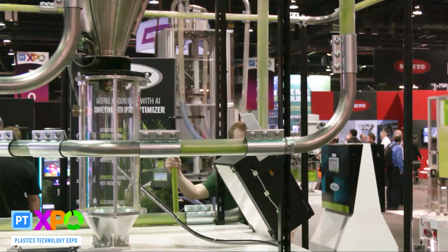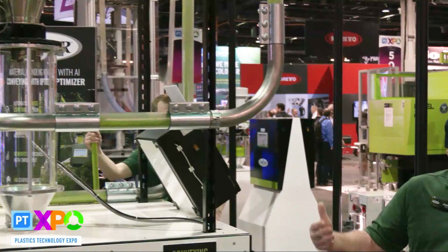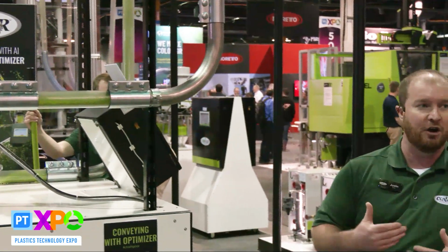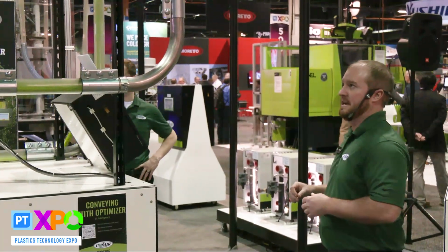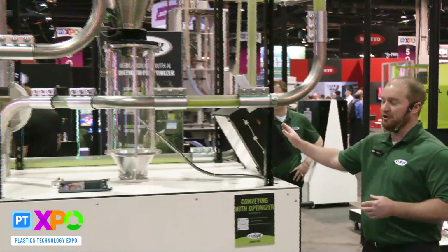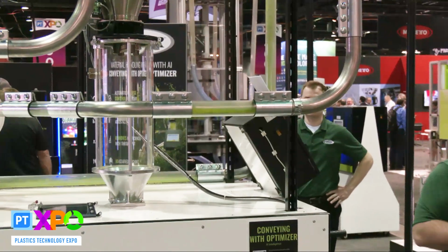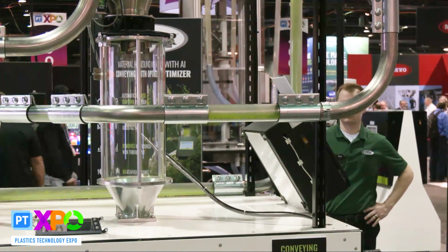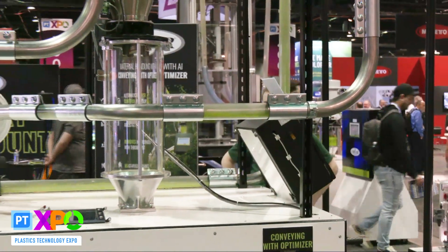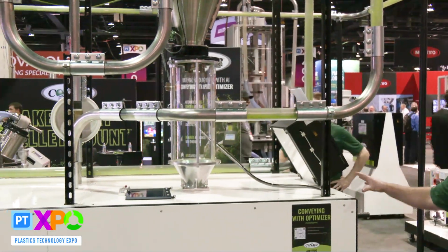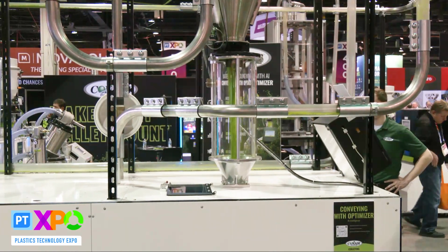Logically, what we expect to happen is that we're going to get more air in the line and our level of material is going to drop. So I'm going to have Chris here throw a vacuum leak. On our control here, we're constantly measuring our vacuum level in the system. So we're now going to be detecting the fact that we have a source of air that is uncontrolled right now.